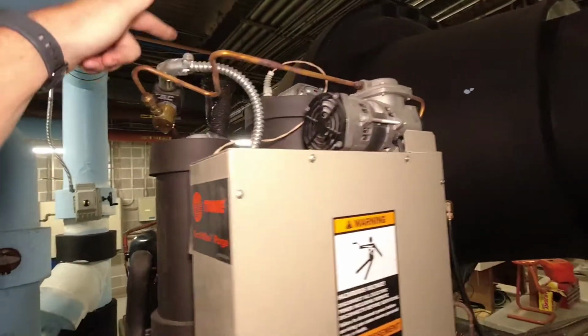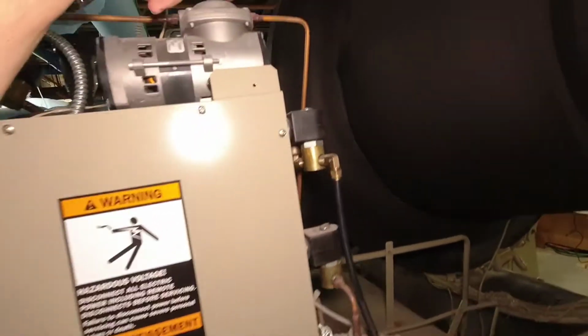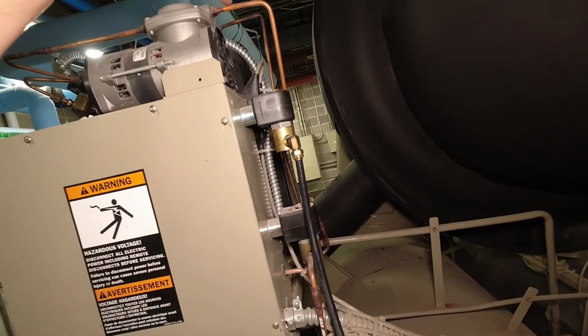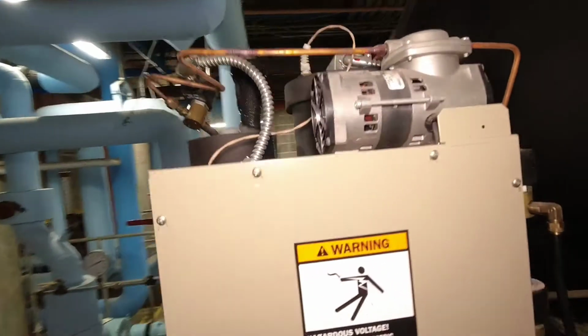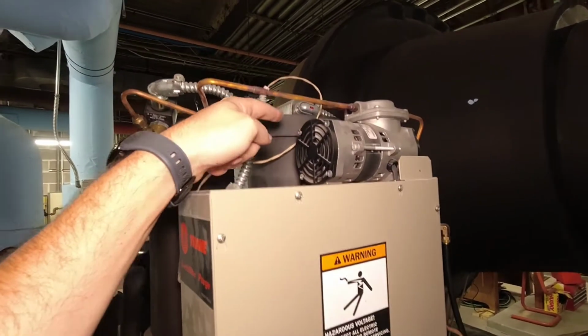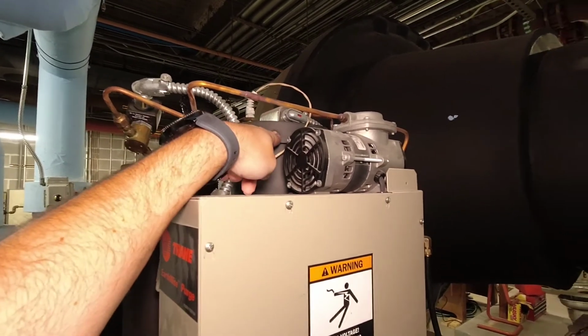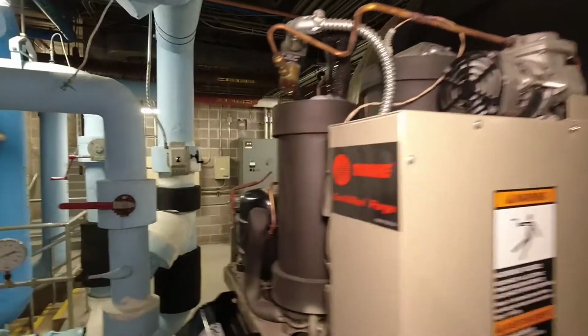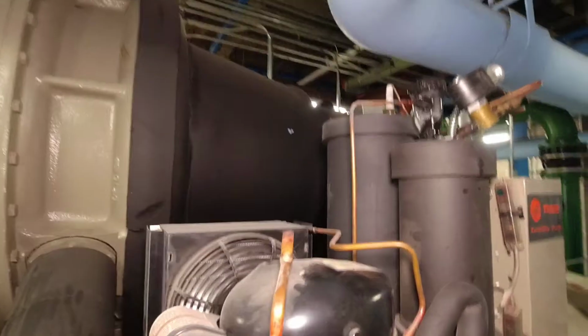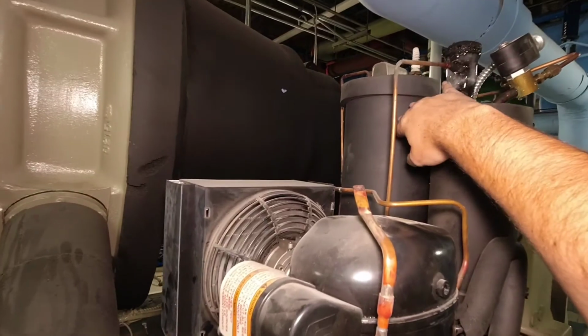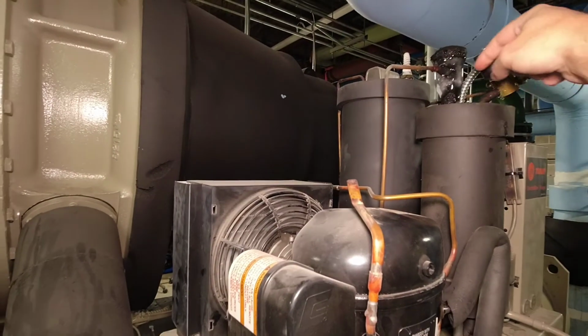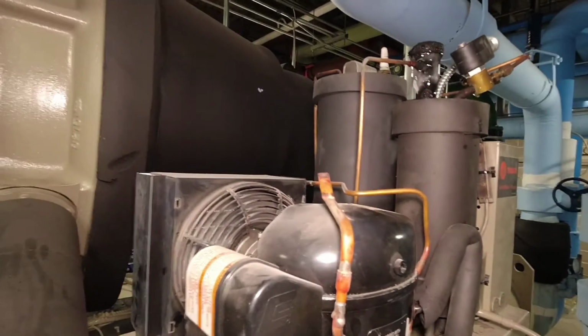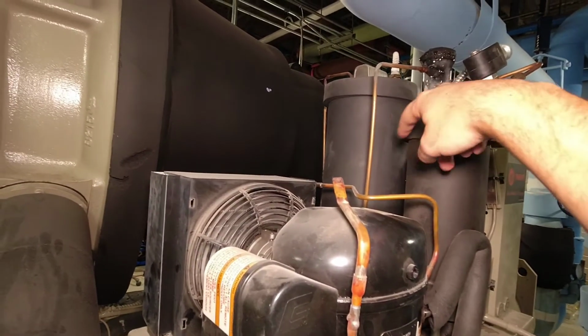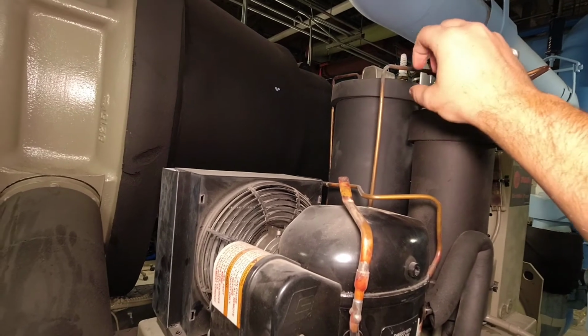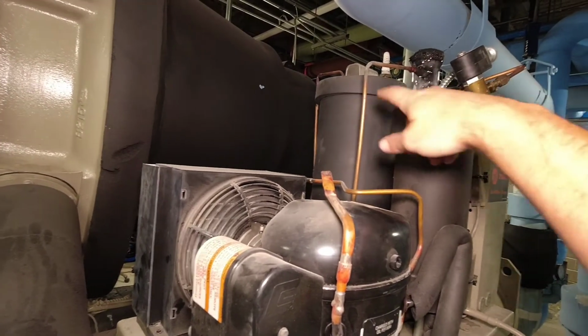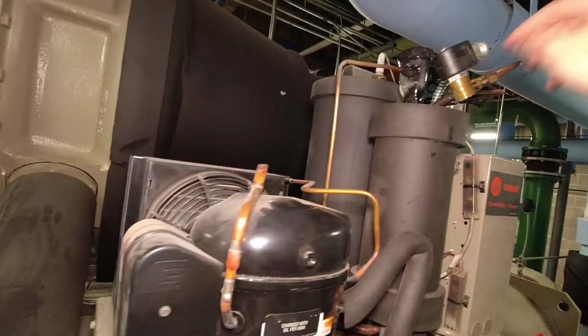We do have some isolation valves for protection, and it's going to go through and reject the atmosphere out of that tank. Now, after it comes out of that tank, it then goes into this regen tank or reclaim tank, however you want to look at it. Not all models have this. Most of your newer ones do. What this tank does is it's got, I think, a carbon type filter in there where it actually collects the little bit of refrigerant molecules that get discharged with the atmosphere.